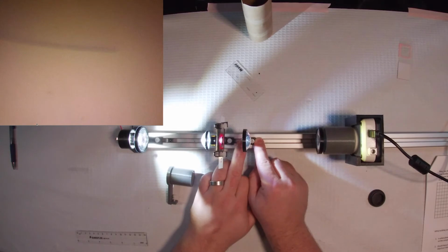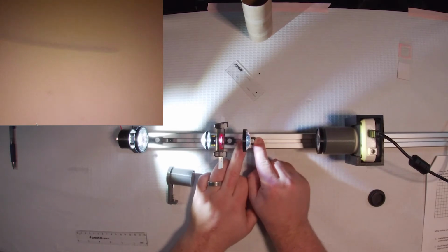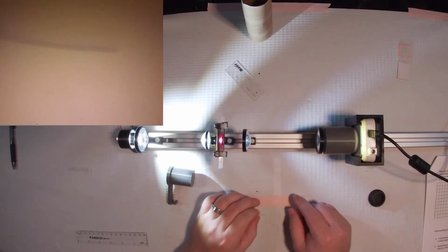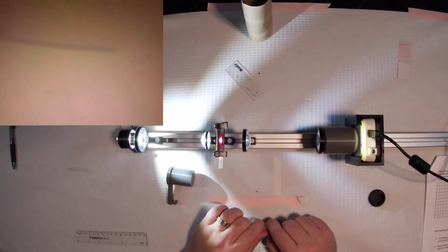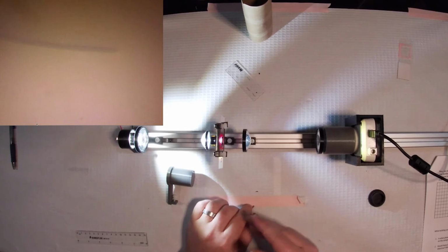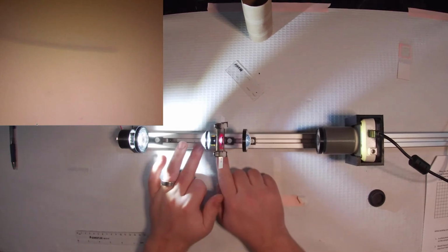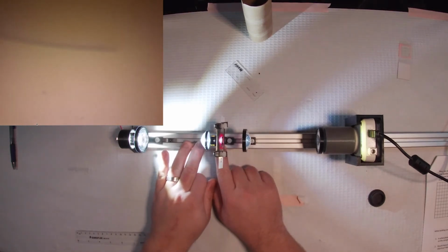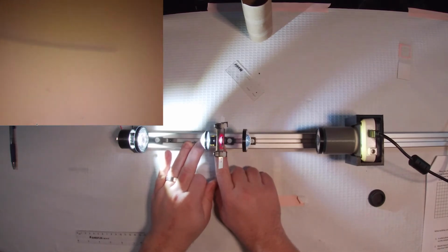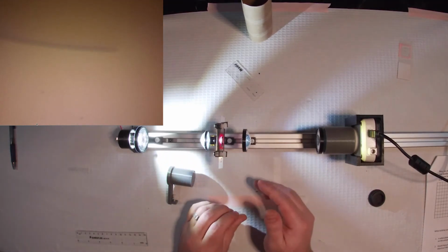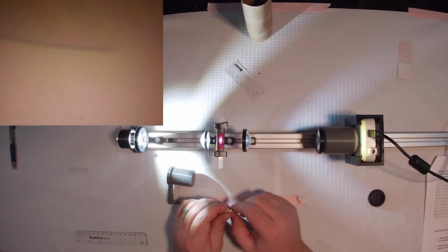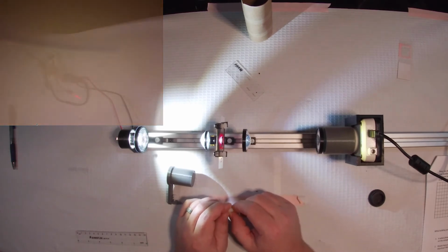You can see that it looks similar to what we've seen in the previous lab, where we have a bright background and dark foreground because the hair is effectively just absorbing the light. It's not going to look as crisp because our condenser has such a high numerical aperture that it does tend to under-illuminate in terms of the field of view, the total area that is picked up by our objective lens, but that's just a flaw in the system.